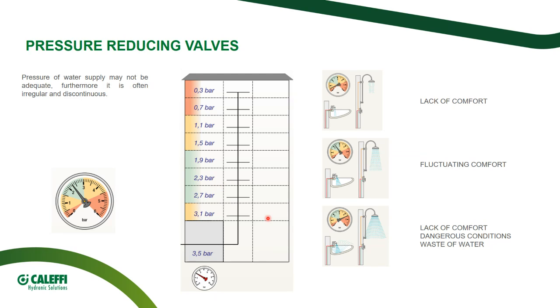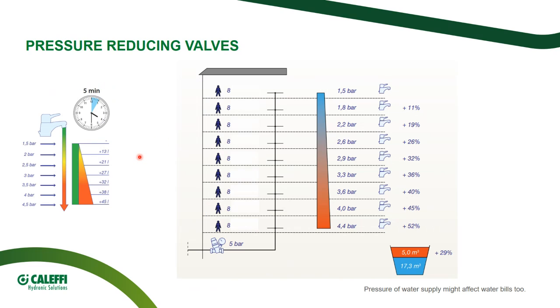On the other hand, at the basement, at the lowest floors of the building, I have a pressure value that is too high. So I have an extra amount of flow rate, a lack of comfort and a potentially dangerous condition. In between, I am in a comfort situation, but it will fluctuate based on the demand of the other stories of the building. Moreover, this is from literature, the result of a simulation of a time lapse of 5 minutes. We have an optimal set pressure value of 1.5 bar, but the pressure throughout the system is not correctly balanced. I am entering with 5 bar from the main connection, and I am granting 1.5 bar to the highest floor. But the floors below are subjected to a too high pressure value.